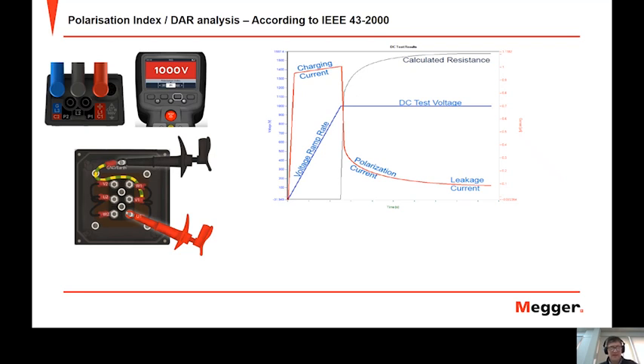IEEE 43 states that if the IR value at 1 minute is greater than 5 gigohms, then the PI test may not be meaningful. They state the PI is dedicated for high voltage machines, but some customers would also perform a PI test on a large low voltage machine. And then some for those low voltage machines would use a DAR or dielectric absorption test instead.